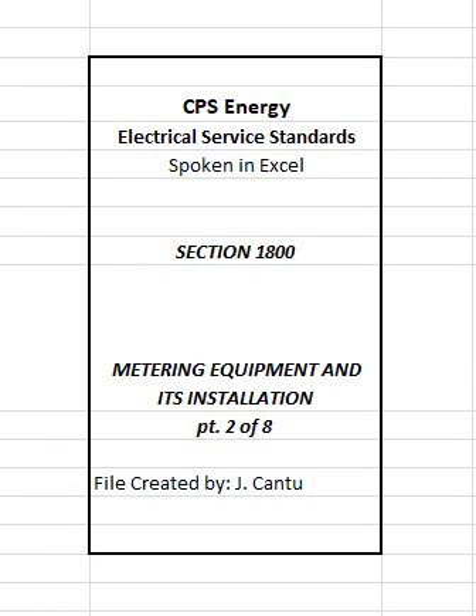1803 Two-instrument transformer rated metering equipment. Instrument transformer rated metering equipment is installed when either the customer's calculated load or service entrance conductor size exceed the maximum rating/specifications of single-position, self-contained meter sockets. CPS Energy furnishes the standard instrument transformer rated metering equipment outlined in Table 1801 of this section.